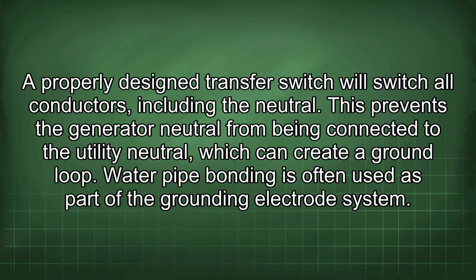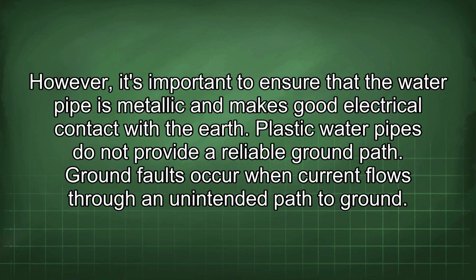Water pipe bonding is often used as part of the grounding electrode system. However, it's important to ensure that the water pipe is metallic and makes good electrical contact with the earth. Plastic water pipes do not provide a reliable ground path.